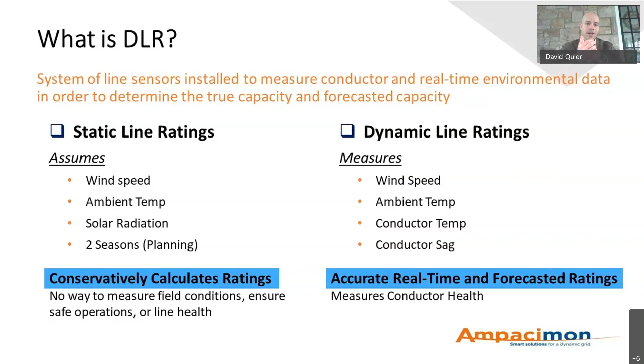With dynamic line ratings we get actual wind speed and ambient temperature for the conditions the conductors are in. We have hilly terrain, with transmission lines along rivers, up and down mountains, and across farmland in Pennsylvania, so conditions vary a lot, but under static ratings they basically all get similar ratings. By capturing wind speed, ambient temperature, actual conductor temperature, and conductor sag through vibration, we can eliminate that conservatism and maximize the use of the system we've built.